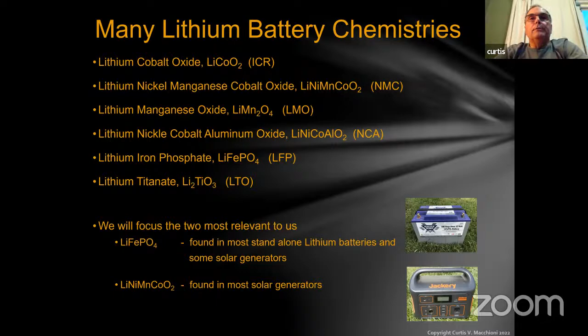Why are these two important? Lithium iron phosphate has a very high number of life cycles, at least 3,000 typical, some say 4,000 or 5,000 full discharge cycles. It also has a very high thermal runaway temperature, and the nominal cell voltage is about 3.2 to 3.3 volts. So you'll find 4 gangs of cells, either a single cell or a gang of cells in series. 4 times 3.2 gives you the 12.8 volts typical of a lithium iron phosphate battery.